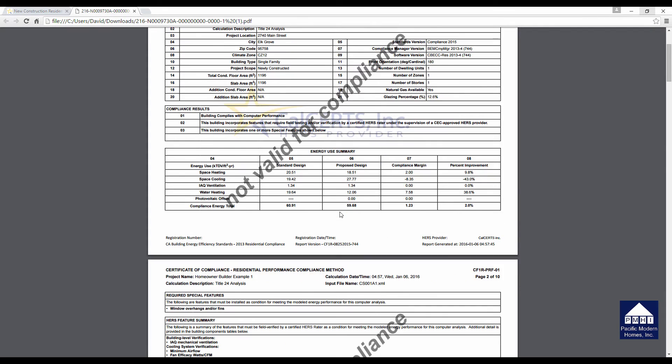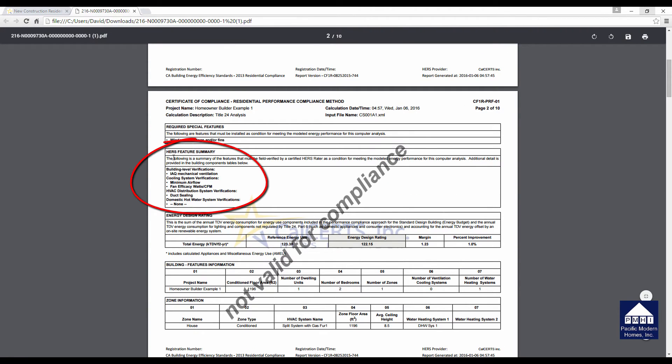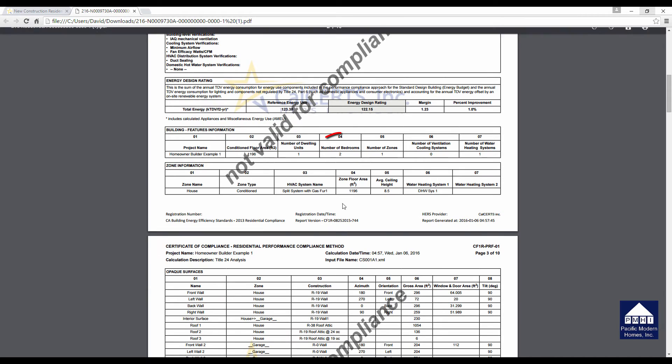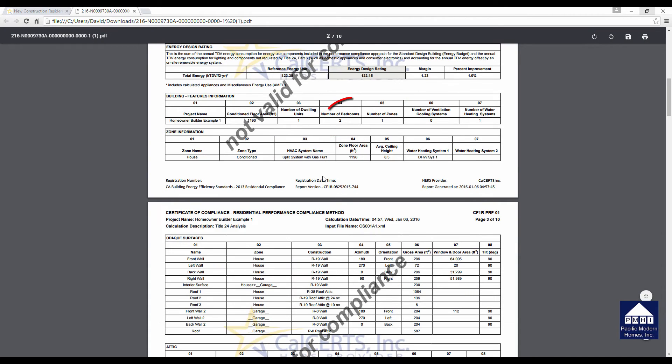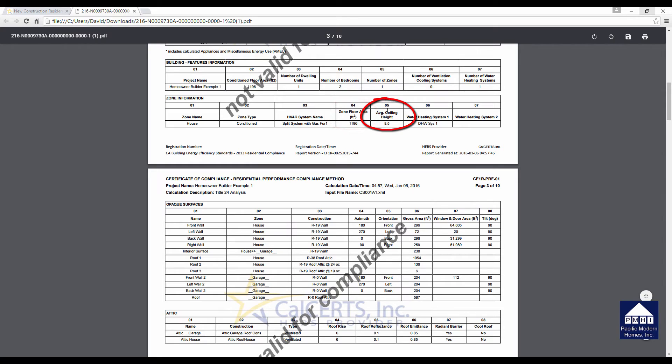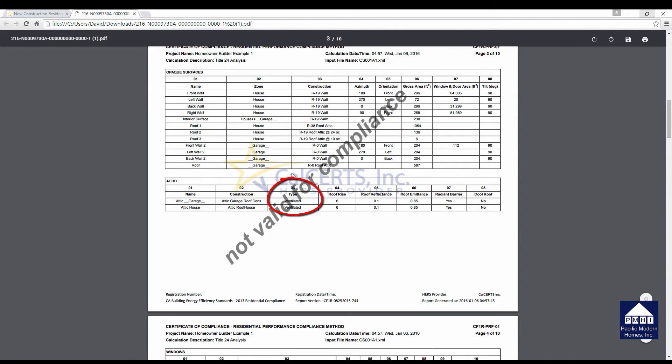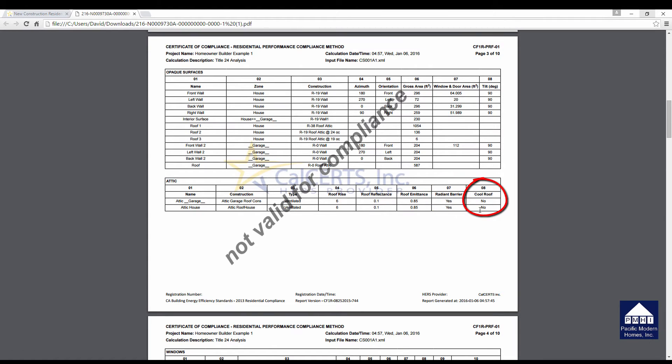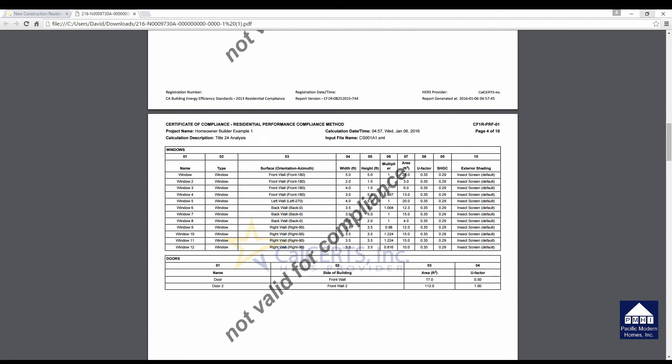The watermark in the background will remain. That's what has to be on the calculations for the building department to accept them. A lot of general information. It's not an easy form to read, but if you look at page two, you'll see a list of the HERS features. This will change for many of the projects, but these are the basic four tests that you will see on almost all new construction. This gives you all the information on the attic, whether it's ventilated or not ventilated. It will give you the reflectance requirements and emittance requirements and whether or not you need to have a radiant barrier installed or a cool roof or both. In this case, this project has a radiant barrier.